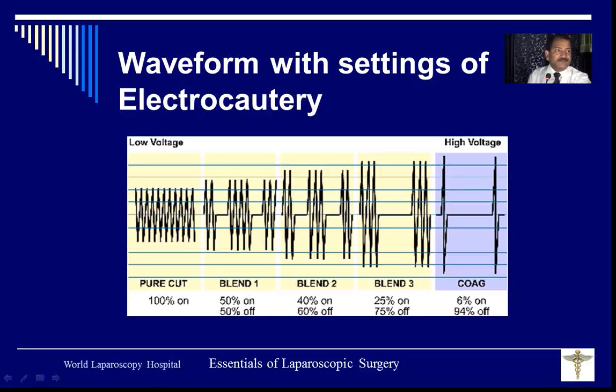Another is coagulation. For coagulation, you have to use the blue pedal. When you press the coagulation pedal, voltage is high and frequency is extremely low. Only 6% of the time your machine is on, and 94% of the time your machine is off.